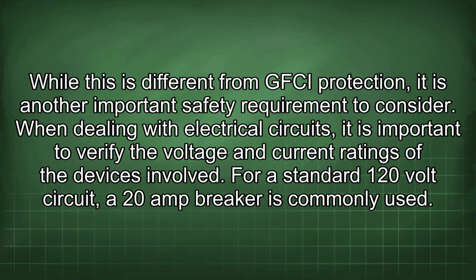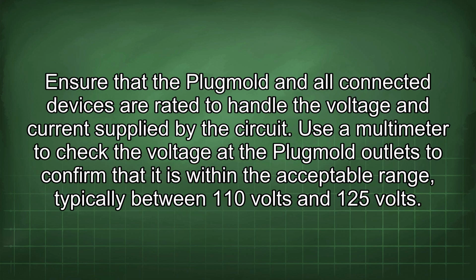When dealing with electrical circuits, it is important to verify the voltage and current ratings of the devices involved. For a standard 120-volt circuit, a 20-amp breaker is commonly used. Ensure that the Plugmold and all connected devices are rated to handle the voltage and current supplied by the circuit. Use a multimeter to check the voltage at the Plugmold outlets to confirm that it is within the acceptable range, typically between 110 volts and 125 volts.